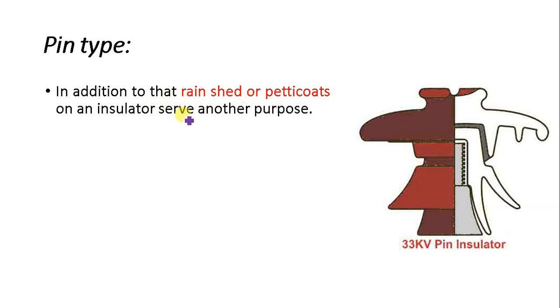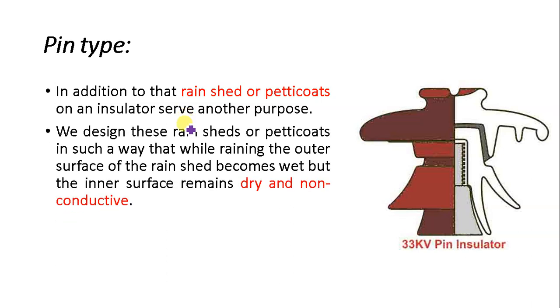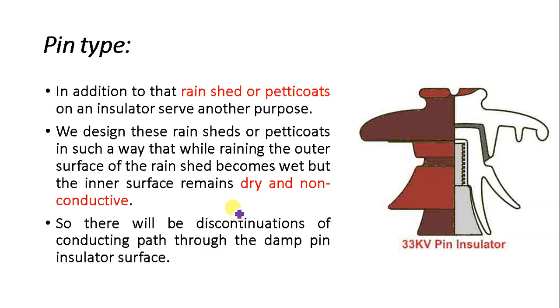In addition to lengthening the leakage path, petticoats on insulators serve another purpose. They are designed such that while the outer surface of the rain sheets becomes wet, the inner surface remains dry and non-conductive. When rain drops fall, the outer surface of the petticoats becomes wet but the inner surface stays dry and non-conductive. That is why the upper part is bigger than the lower part.